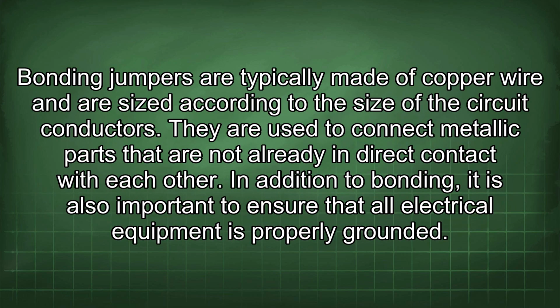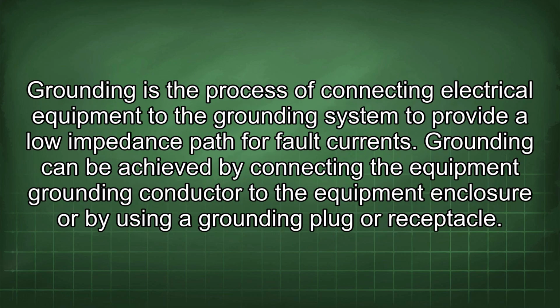Bonding jumpers are typically made of copper wire and are sized according to the size of the circuit conductors. They are used to connect metallic parts that are not already in direct contact with each other. In addition to bonding, it is also important to ensure that all electrical equipment is properly grounded. Grounding is the process of connecting electrical equipment to the grounding system to provide a low impedance path for fault currents. Grounding can be achieved by connecting the equipment grounding conductor to the equipment enclosure or by using a grounding plug or a receptacle.